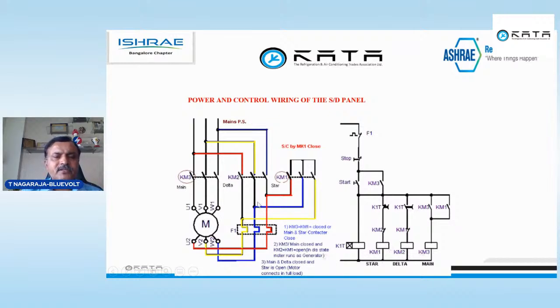Whenever you want to do some fault finding or repair work, please remove this star short we have given here. Then you check all the winding, this starter wiring, everything, anything burnt out. If you are repairing or troubleshooting, you remove this star connection, you check, then you put it back. Otherwise, what will happen? Suppose delta and star contactors are engaged together, it will definitely get a blast because all three phases will be a dead short here. So during troubleshooting you open the short, then troubleshoot, check thoroughly, ensure that this is working properly, then you put the short back. It will ensure the safety of the repair.